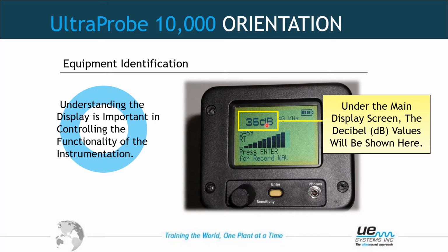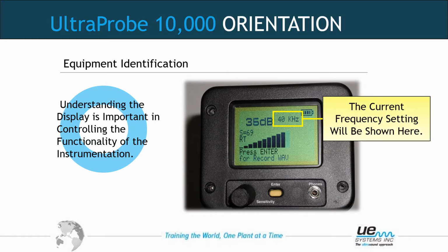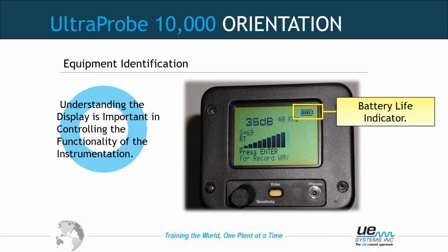Here, under the main display screen, the decibel values will be shown. If not shown, there will be arrows telling you which way to turn the sensitivity so that the Ultraprobe 10,000 may form a digital decibel on the screen. The frequency of this unit is 20 kilohertz to 100 kilohertz in increments of 1 kilohertz. The battery indicator, telling you how much battery remains. As you get down to 1 bar left in that graph, it's time to finish up what you're doing and start recharging or grab another battery.